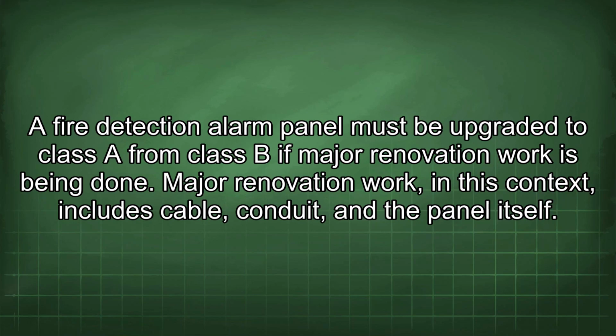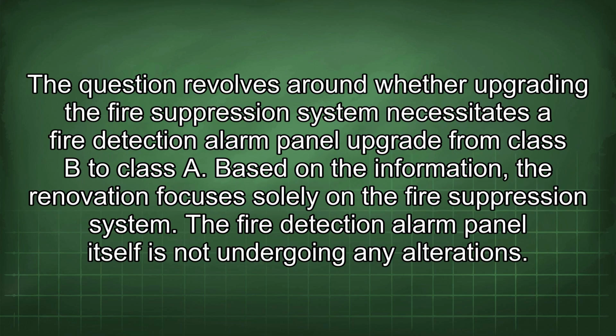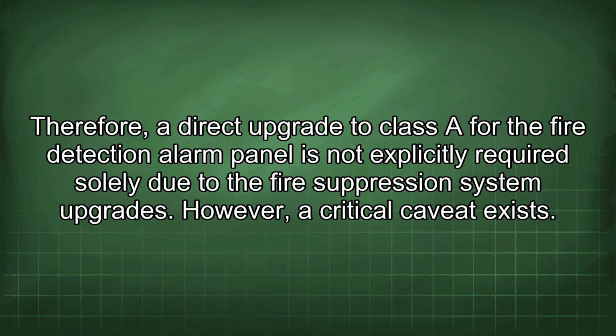A fire detection alarm panel must be upgraded to Class A from Class B if major renovation work is being done. Major renovation work, in this context, includes cable, conduit, and the panel itself. The question revolves around whether upgrading the fire suppression system necessitates a fire detection alarm panel upgrade from Class B to Class A. Based on the information, the renovation focuses solely on the fire suppression system. The fire detection alarm panel itself is not undergoing any alterations. Therefore, a direct upgrade to Class A for the fire detection alarm panel is not explicitly required solely due to the fire suppression system upgrades.